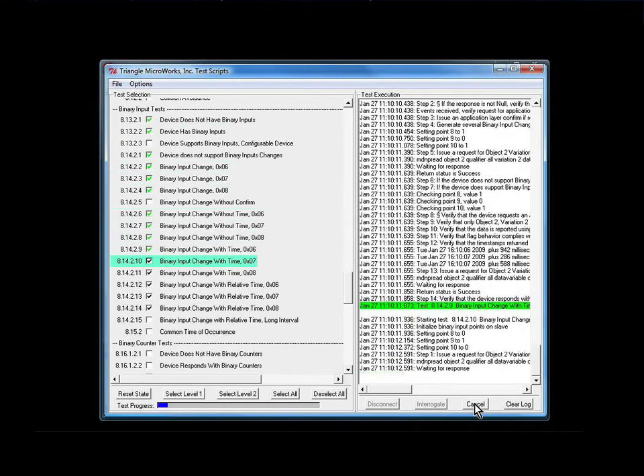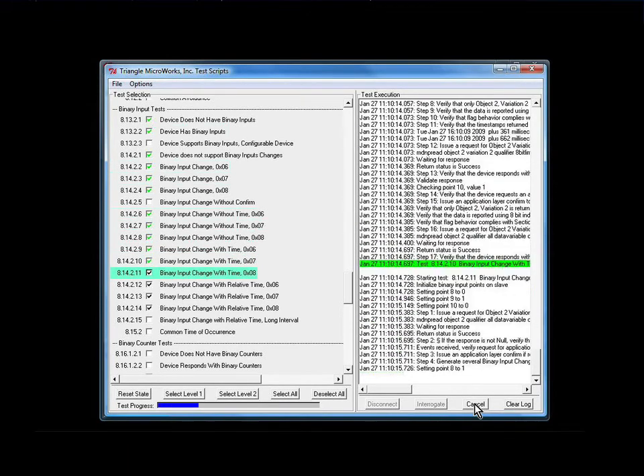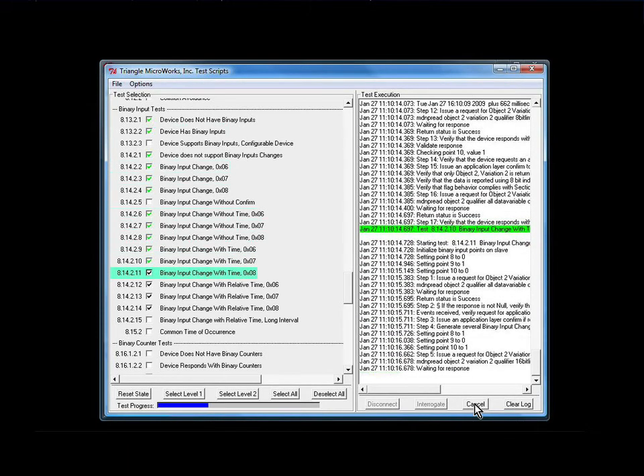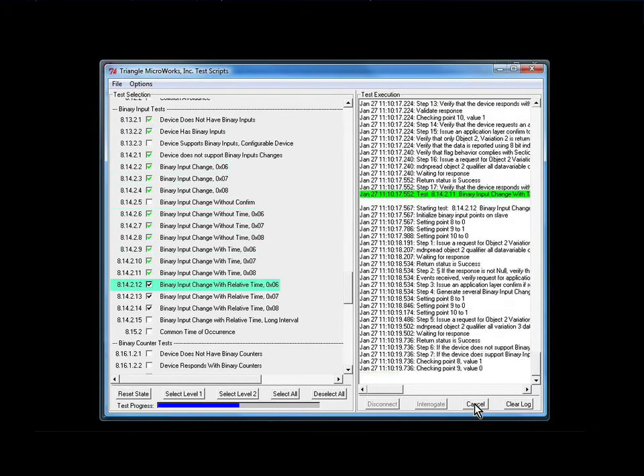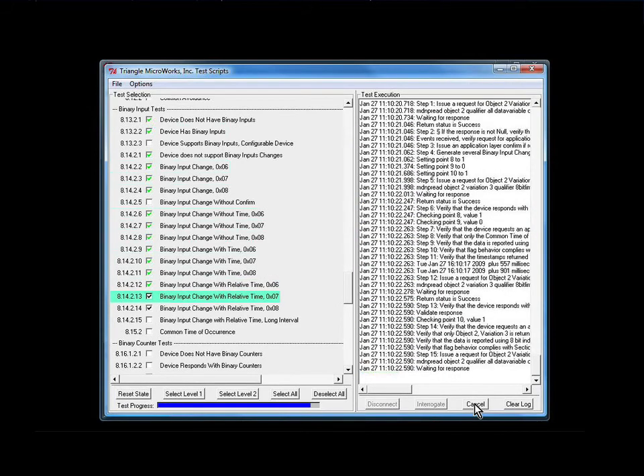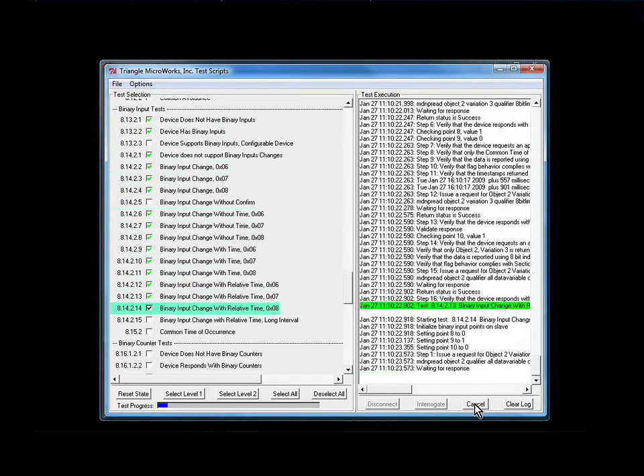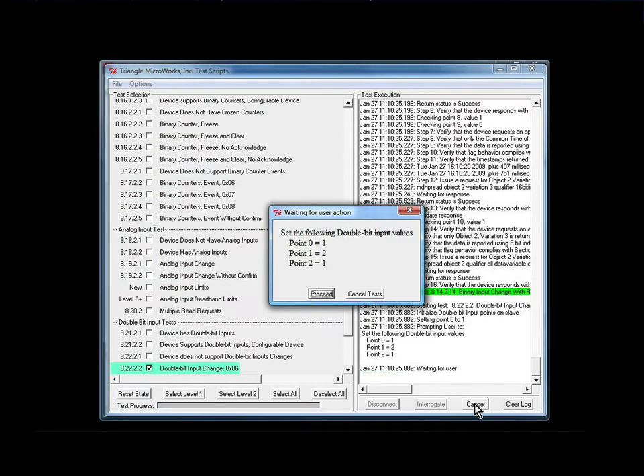What's happening is various input conditions need to be set up to run the test, and the test harness is automatically configuring those input conditions through the Omicron CMC 156. The binary input tests have now completed, and we've moved on to the double-bit input test.